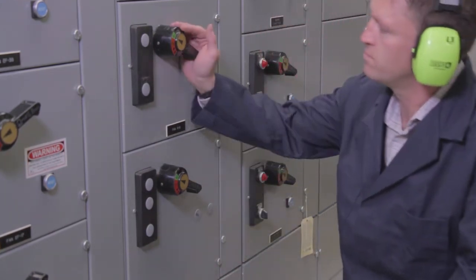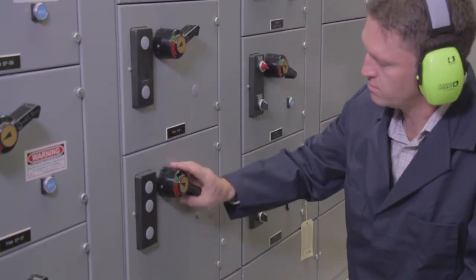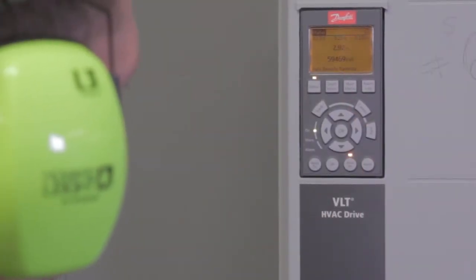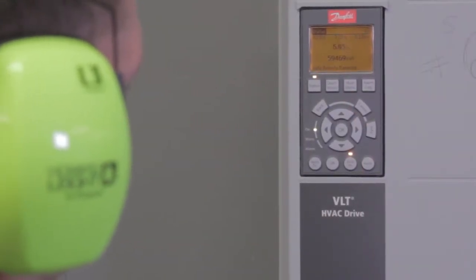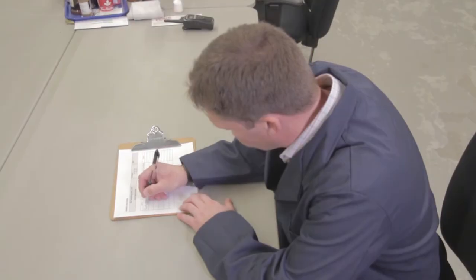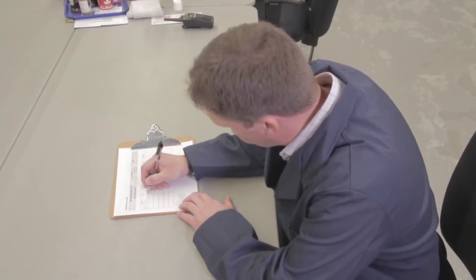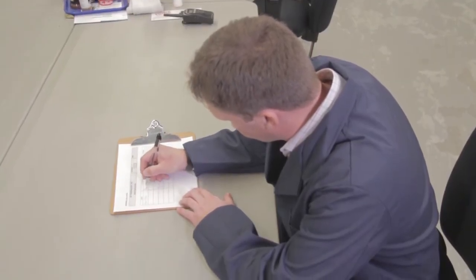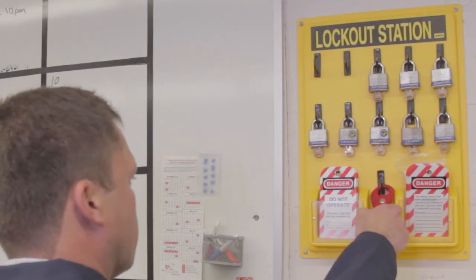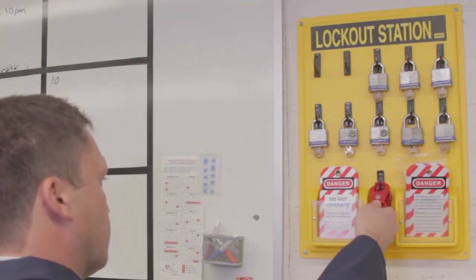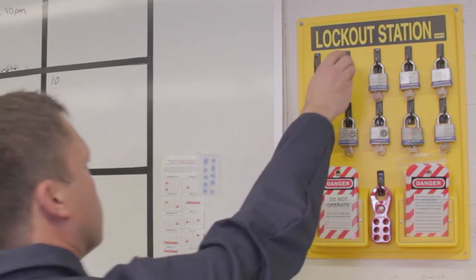Restore energy. Sometimes people take off the locks but forget to restart the equipment. Confirm that the equipment is functioning after energy has been restored. And log the event in the caretaking logbook and your maintenance log for that piece of equipment. Return the lock, hasp, and key to the lockout-tagout board and discard the used tag.